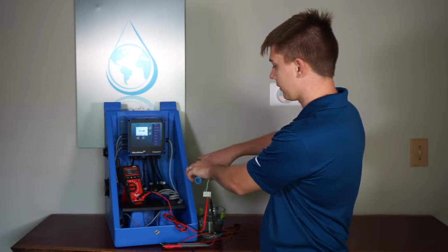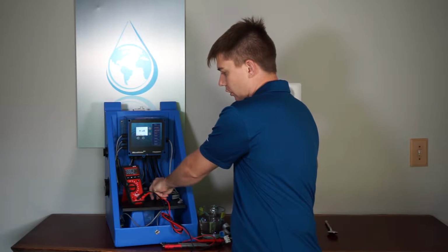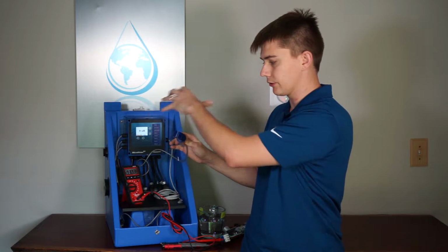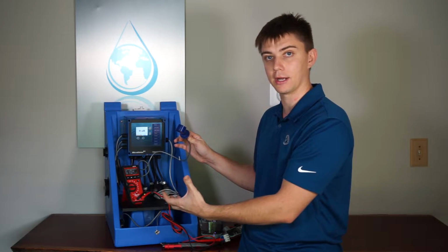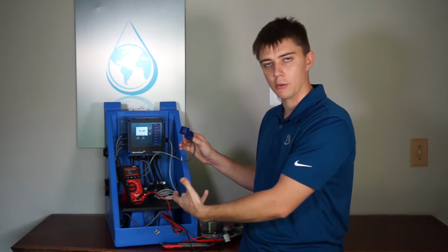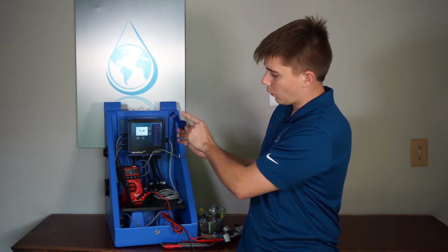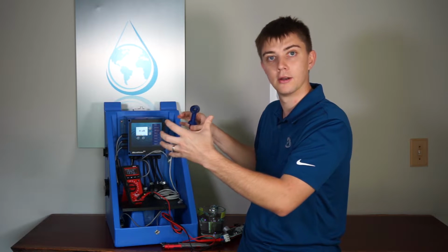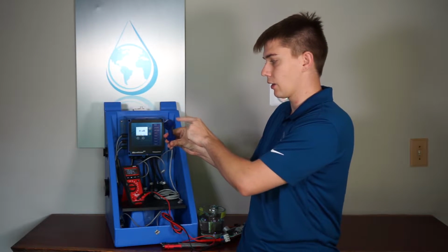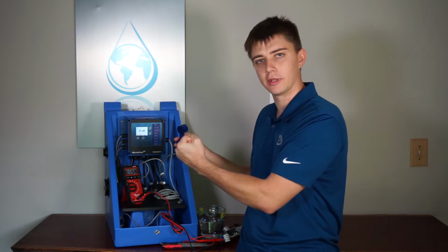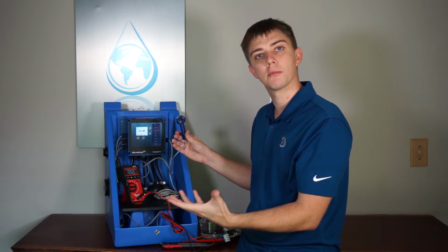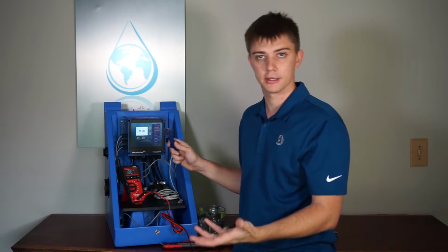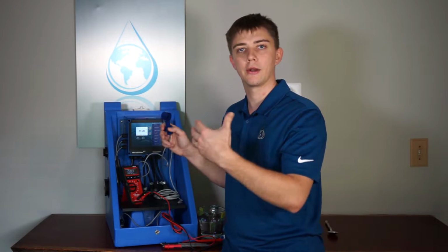I have another style of conductivity probe. This is a toroidal style. So this isn't contacting. This has a magnetic field. And based on the intensity of that magnetic field, it's determining conductivity. So you have one half of your toroid basically as a little antenna emitting a magnetic field, and then another receiving side receiving that magnetic field. If it's a strong magnetic field, then you know you've got a conductive mix. If it's a weaker magnetic field, you're in a pretty pure and non-conductive environment.